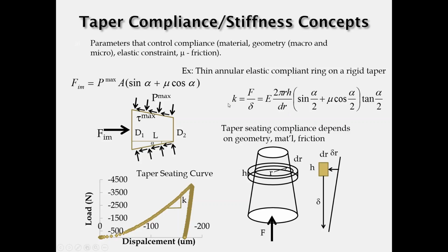In this example, I'm showing a stiffness parameter K for a thin annular ring being pushed down onto a rigid trunnion. The equation for that engagement or stiffness has the modulus of the ring, features of the geometry of that ring, the taper angle, and the coefficient of friction. All of those go into this slope parameter that is measured when you seat the head onto the neck.